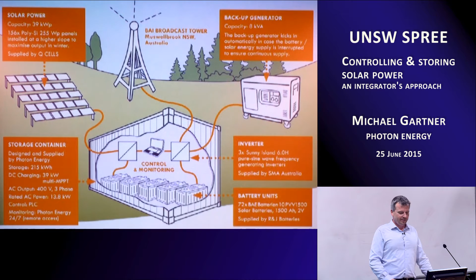We used lead-acid batteries for this system, and there were some considerations as to why we chose that technology, because we did look at lithium-based technologies as well. The considerations were that we had to have a technology which was highly available, and highly available in Australia, so we selected a manufacturer with a very strong distribution base in Australia. The reason is that if you do need to replace things, you want to have supply available at any point in time.